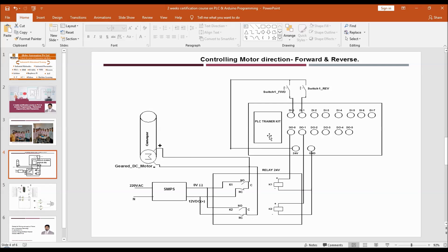In addition, even if the operating voltage of the DC motor were 24V, it is not recommended to connect the motor directly to the PLC. Because motor power is high, the PLC output may be transistor output or small power outputs. So we cannot drive the motor directly from the PLC kit.